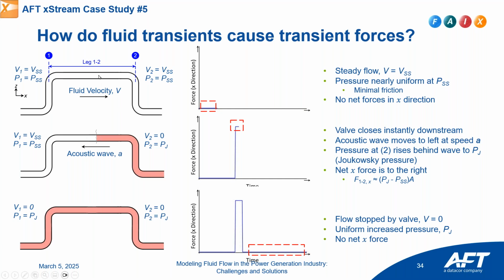When there's a steady state velocity going through, there is balance in the system—all the forces add up to zero, so there's no movement on the piping, no transients causing movement. Now, what happens if you get a transient, for example a quick closure of a valve?